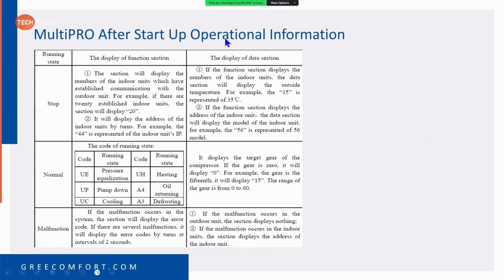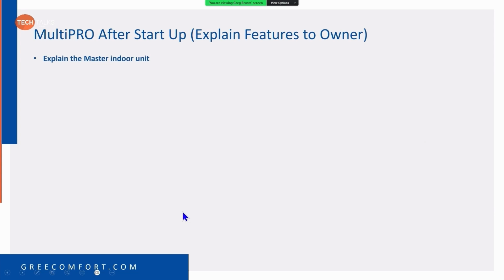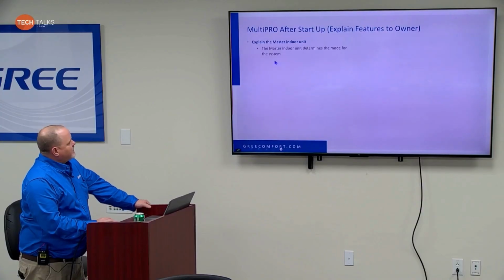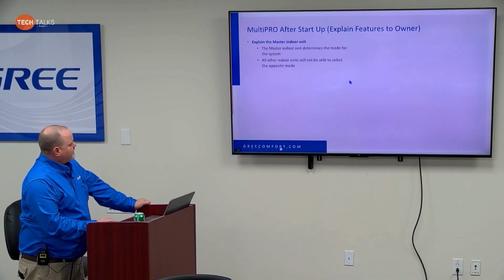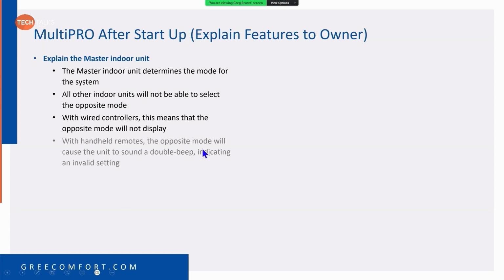So after startup operation of the information, I always like to show this slide because it gives you these running parameters. UE is pressure equalization, UP is pump down, UC is cooling, UH is heating, A4 is oil return, A3 is defrost. So make sure you explain to the customer which unit is the master, the main indoor unit. Remember, that's going to control your mode. Master unit determines mode of system. All other indoor units will not be able to select the opposite mode. With wired controllers, this means that the opposite mode will not display. With handheld remotes, the opposite mode will cause the unit to sound a double beep indicating an invalid setting.